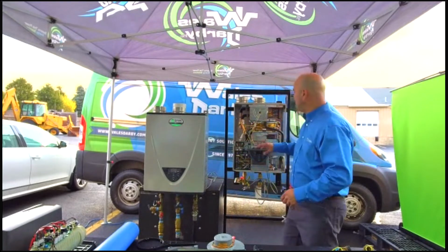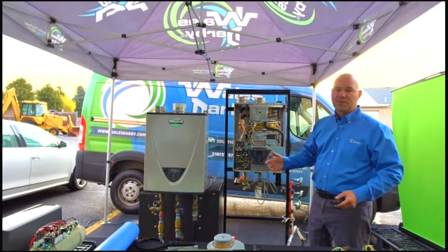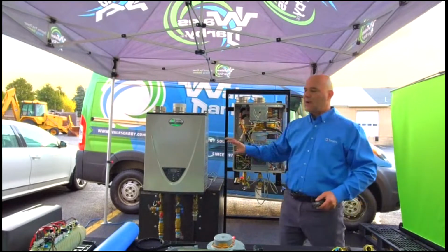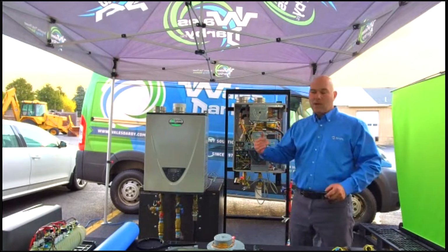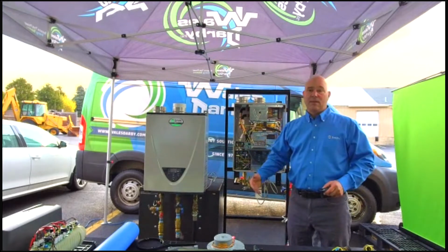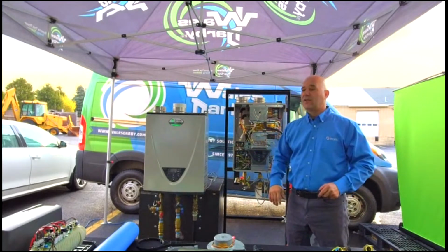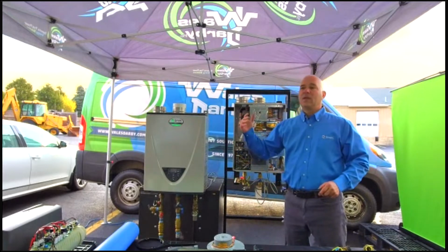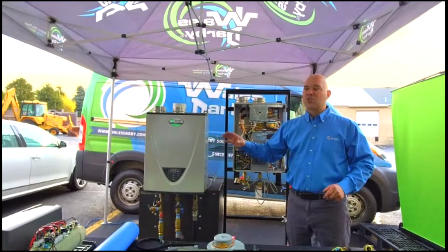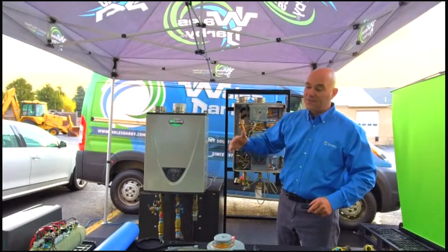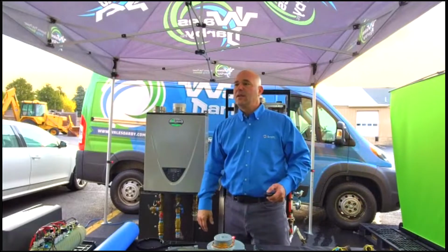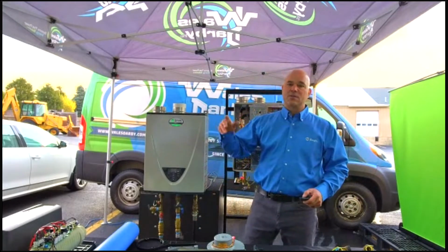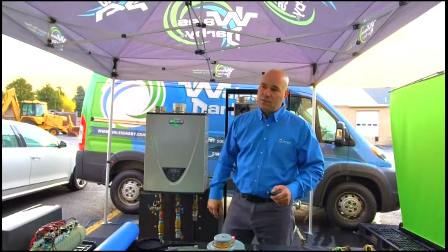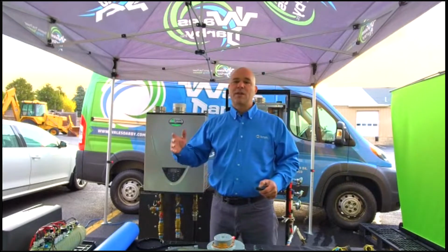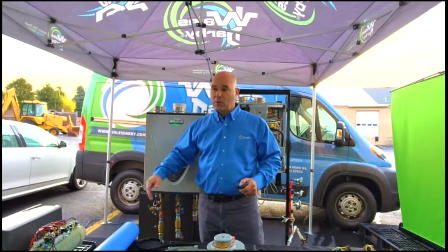So if you haven't done a tankless before, it's obviously extremely important to take a look at the manual. There's a lot of nuances about all these different tankless that are out there. Understand the brand that you're using. Again, we're the A.O. Smith guys, so we appreciate you using ours. But whatever you're using, just make sure you're checking to see that everything you're doing is correct to the manufacturer's specifications. So on the electric side, we talked about earlier, we have 208 volt, we have 230 volt electric tankless in 1 chamber, 2 chamber, and 4 chamber.